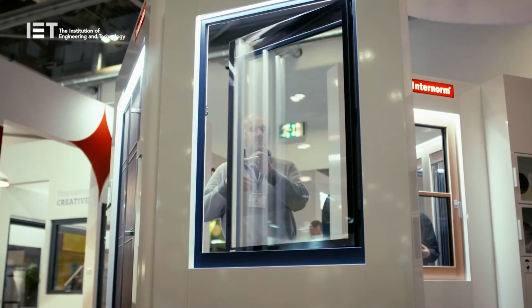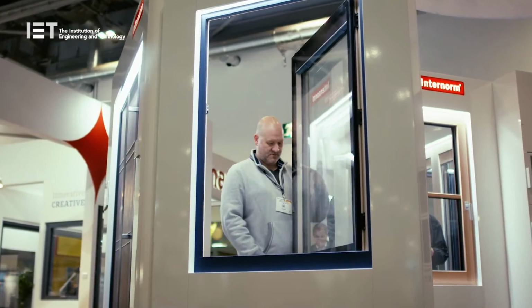So looking at the energy modelling and looking at the archetype that we've got, the occupancy and the usage, that enabled us then to sort of prioritise the M&E systems. So for example, with these particular properties, when we evaluated things like MVHR systems, it wasn't an easy fit because the properties didn't lend themselves to it very well, and that capital cost could be used more efficiently with battery storage, for argument's sake.